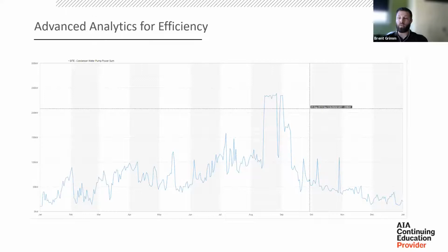Another example that we have here, looking a little more advanced use of the analytics for efficiency. For this example, we're actually using key performance indicators, which are roll-ups of certain data over a period of time. So using a condenser water pump power sum KPI at a medical facility, we're able to catch this major efficiency issue where a bug in the programming caused all condenser water pumps, I believe it was 6 of them, to enable and go to 100%.